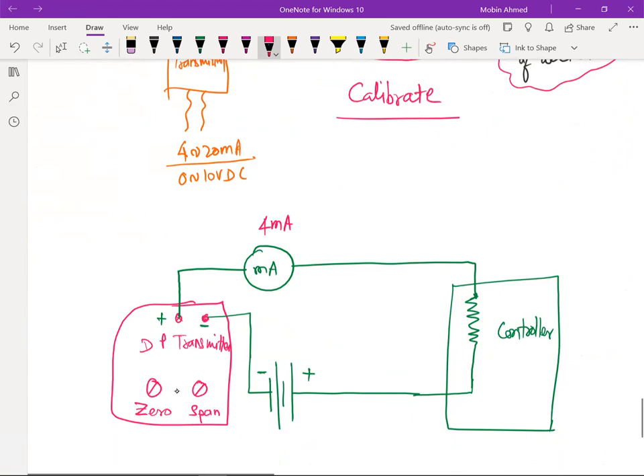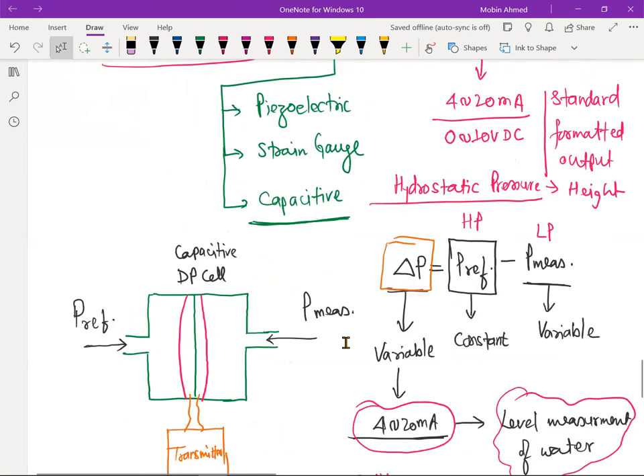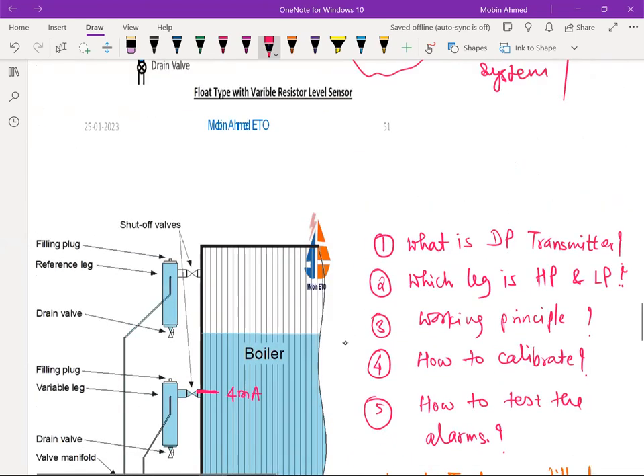If it is not reading 4 milliampere, then adjust it with the zero potentiometer. So this is the potentiometer here, zero. It should be adjusted with that. Now next one. Again, you have to raise this water level up to here. And here it's supposed to read 20 milliampere. You need to raise this water level up to here, and this is supposed to read 20 milliampere.